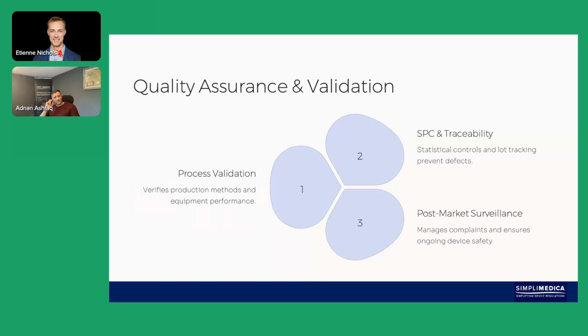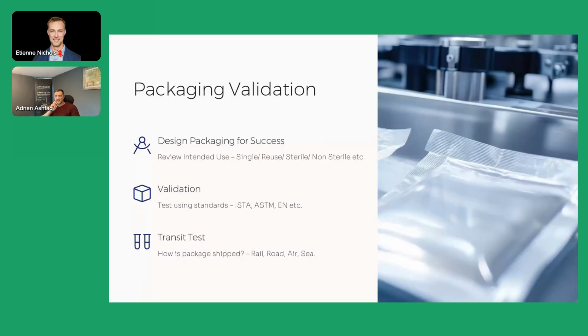Okay, so then we've also got packaging validation, which is another very specific area. Designing packaging for success. Is the device single use? Is it reuse? Is it sterile? Is it non-sterile? Your manufacturing process has to allow for the requirements for these, whether it needs to be done in a clean room environment, etc. What level of clean room? What validation standards do you need to apply? If you're doing transit testing, your design validation, you've got to apply these standards. Don't think of that as limited to design verification and validation before design transfer, because once your device is in manufacturing beyond design transfer, you have to make sure that the processes, even packaging, are fit for purpose.